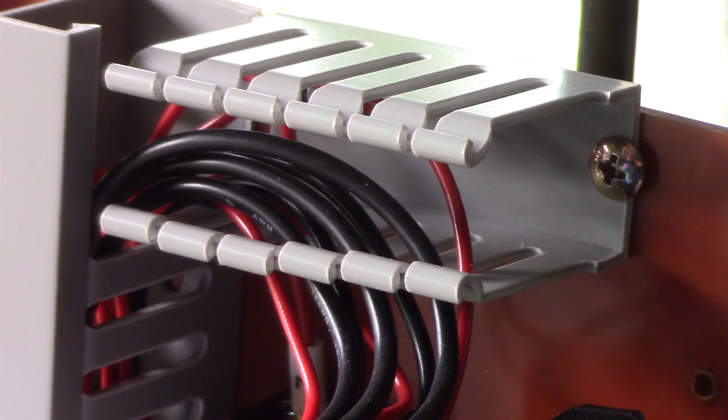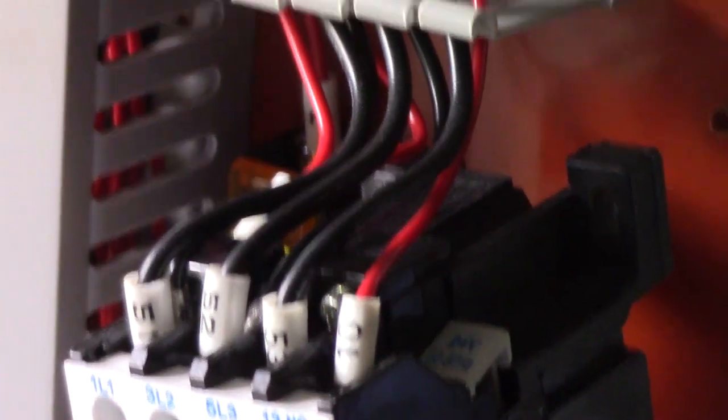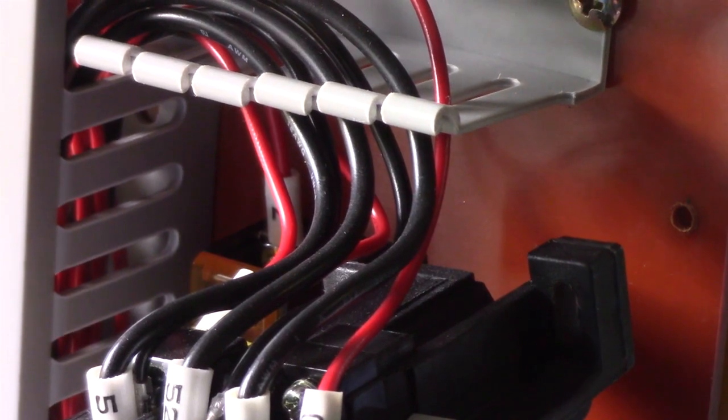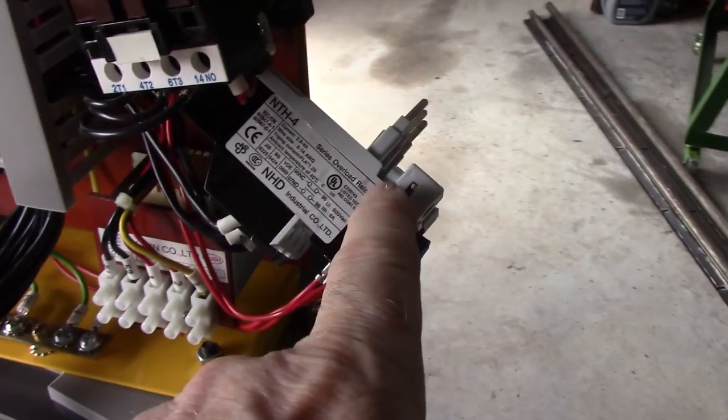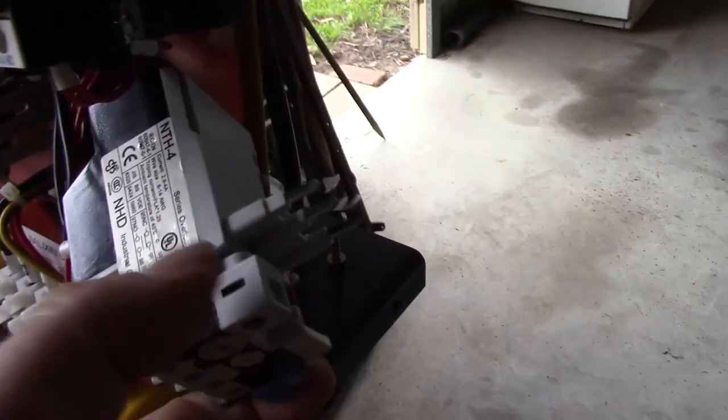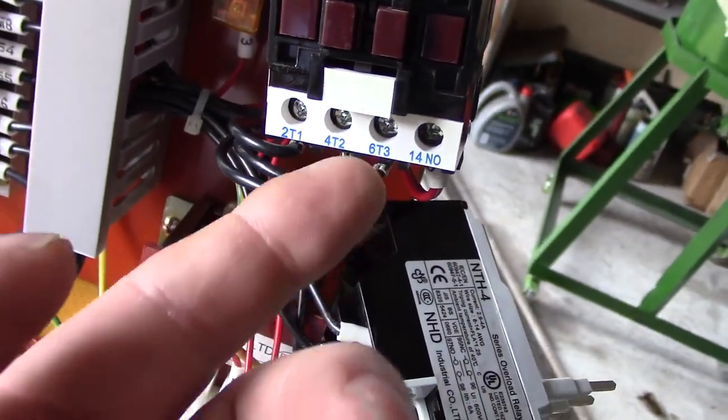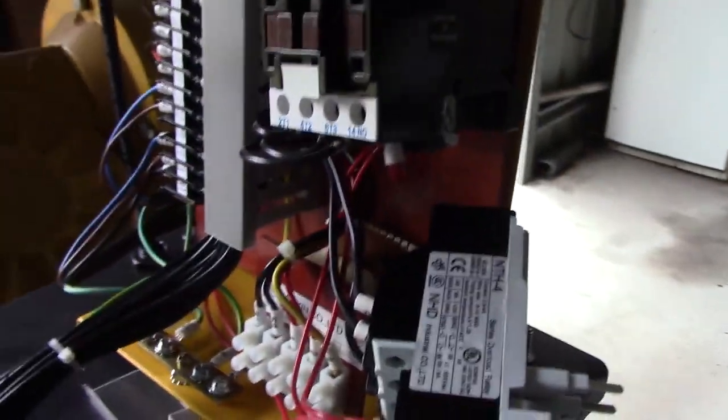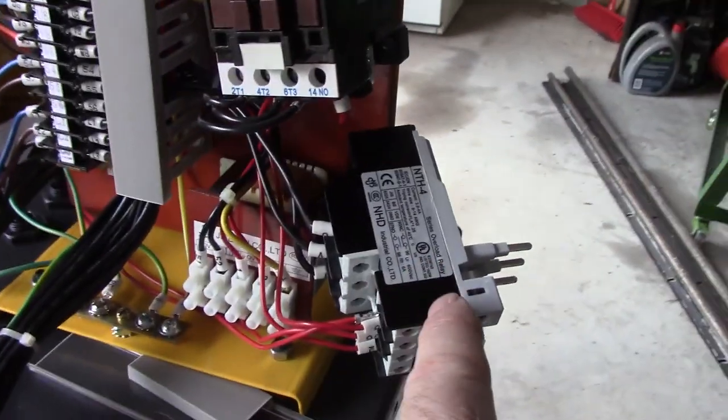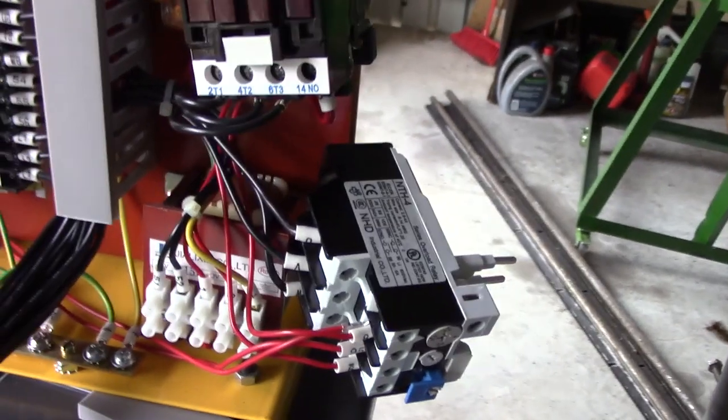This is the thing that I'm doing - I am going to take a series of still pictures of just how everything fits together so I can take it apart and get that replaced. And that's got the overload relay separated from the solenoid switch. These three wires here are held in by these three screws, which also hold in these three connectors here on the overload relay. You have to hold those wires into place, push those connectors up into those three 2T1, 4T2 and 6T3 connection slots, and then do it all up. That's what I'll be doing once I replace this relay. I'm going to leave it sit there like that so that when I get the new one, I can just take it wire for wire and make sure I don't make any mistakes.